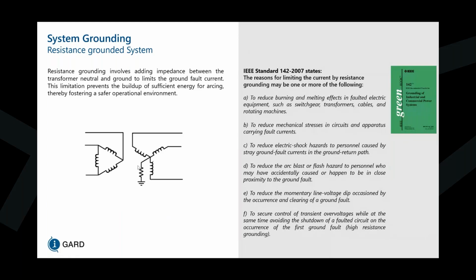And on the right, we have the IEEE standard green book. It indicates the reasons for limiting the current by resistance grounding may be one or more of the following. To reduce the burning and melting effects in faulted electrical equipment, such as switchgear, transformers, cables, and rotating machines. To reduce the mechanical stresses in circuits and apparatus carrying fault currents. To reduce electrical shock hazards to personnel caused by stray ground fault currents in the ground return path. And to reduce the arc blasts and hazards to personnel who may have accidentally caused or happen to be in close proximity to the ground fault.